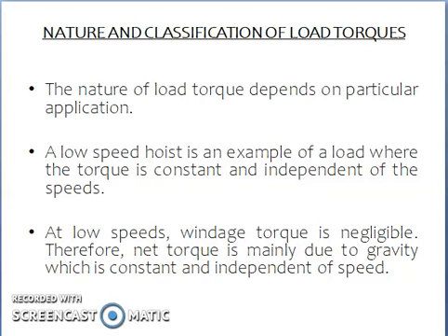Next, if we discuss the nature and classification of load torques, there are various classifications. The nature of load torque depends on the particular application, as we discussed previously. Say, for example, a low speed hoist. It is an example where the torque is constant and independent of speed. Here, at low speeds, the windage torque is negligible.